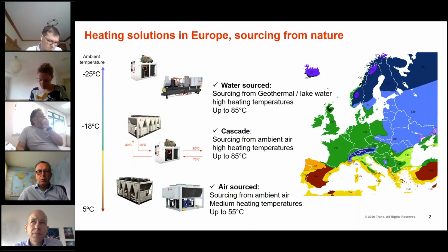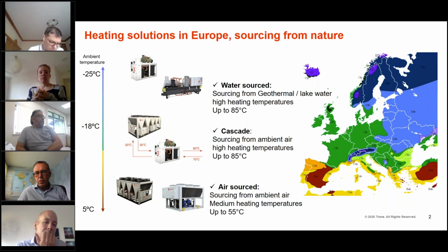Initially, as an introduction to the technology matching different requirements, I chose to show you the applications that can be used in different ambient conditions. Heat pumps are always thought of as being used to source energy from ambient sources, so that's ambient air or water sources. And ambient air, as we know, across Europe, depending on the climate, can vary a lot at winter time. So depending on those climate conditions, there are different ways to attach the heating process to the ambient source. To give a bit of understanding, we know that air-to-water heat pumps are commonly used across the Mediterranean areas, because that's where the ambient temperatures allow easier access to the energy of air by an air-to-water heat pump.